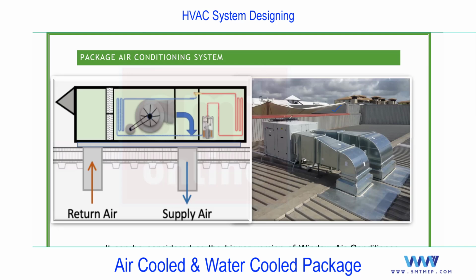So here in package, first of all, the components: compressor and condenser. This we can consider as one section. In the second section, you'll find the evaporator, the fan motor and a blower. And you'll find the expansion also. Expansion can be in section 1 or section 2, because we are not bothered about the noise now, because this complete unit is placed outside the building. In case of split, this expansion you'll find in the outdoor to reduce the hissing noise in the indoor. But in this case, depending on the model, it can be on this side or this side. So these four components are in one unit with two separate sections.